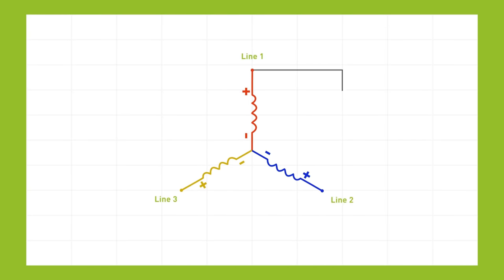For three-phase, you connect line 1 to line 2 and get 208 volts. At the same time, you connect line 2 to line 3 and get 208 volts, and you connect line 3 to line 1 and get 208 volts.